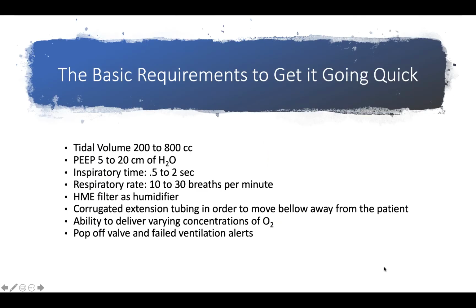The specifications needed at the minimum for this bridge ventilator to work are as follows. It must be able to generate a tidal volume in the range of 200 to 800 cc's to meet the ventilatory needs of most of the adults. In addition, we should be able to apply a PEEP of between 5 to 20 centimeters of water. This can be conveniently achieved by attaching the PEEP valve to the expiratory end of the ambu valve, which is usually the case. The ventilator should be able to deliver the tidal breath with the inspiratory time frame of 0.5 to 2 seconds. And the ventilator should be able to deliver a respiratory rate between 10 to 30 breaths per minute.